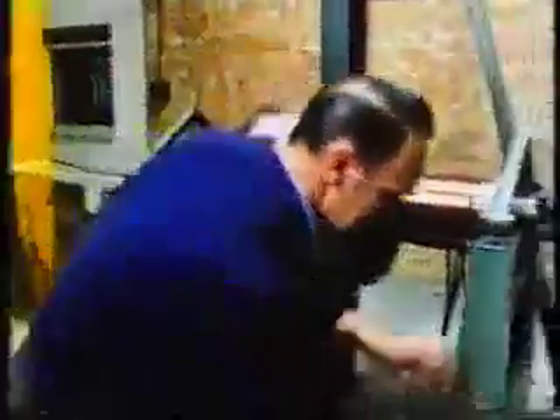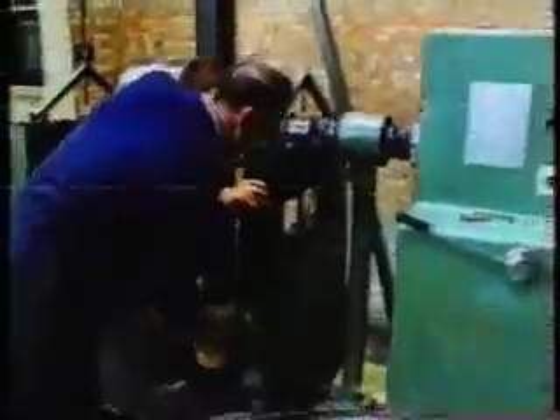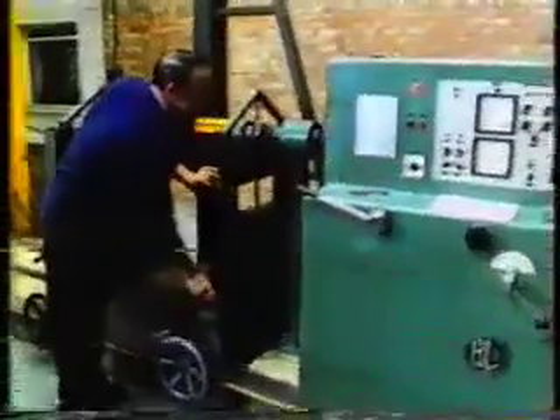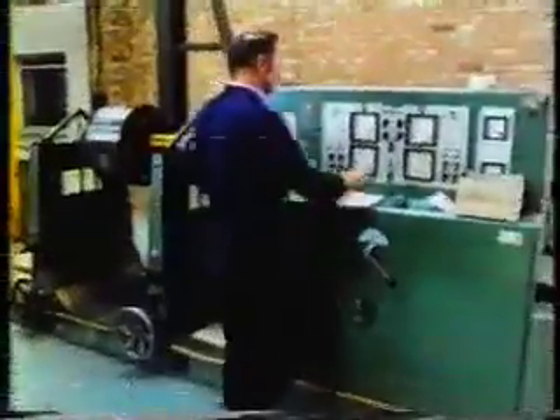The completed rotor assembly is balanced to a high degree of accuracy. While it spins, out-of-balance forces are detected and corrective balance weights are added. The stator frame supports the terminal box which will house the control equipment. Now the final assembly. Positioning the rotor inside the stator is carried out with considerable care.